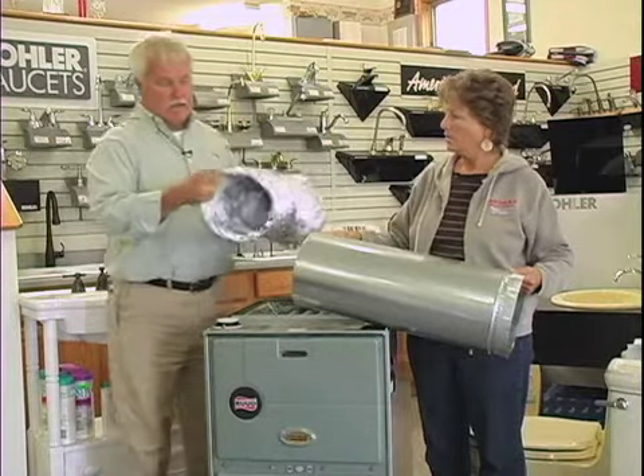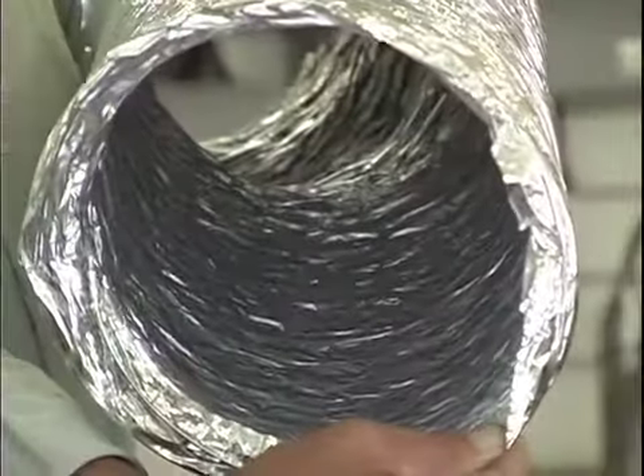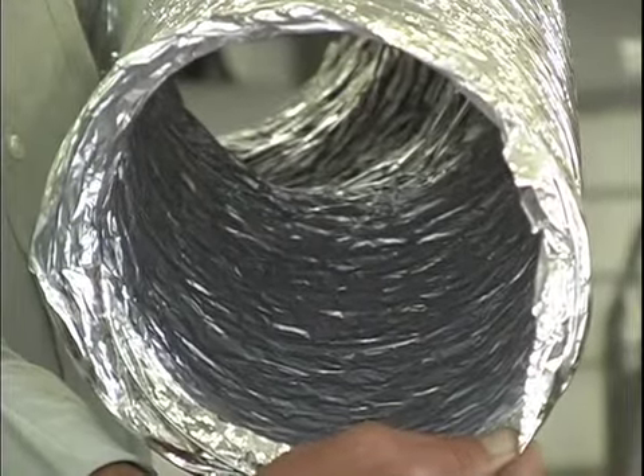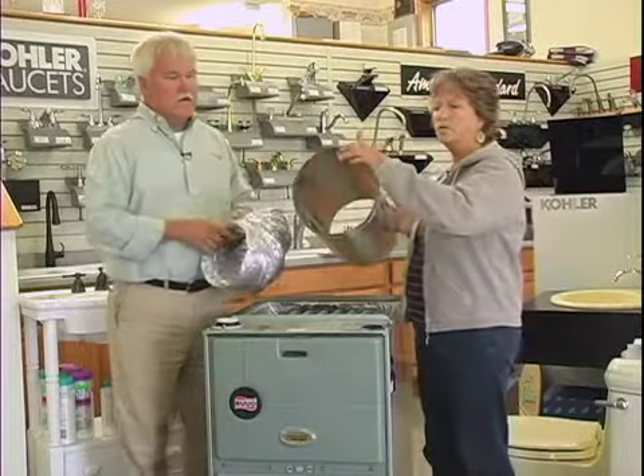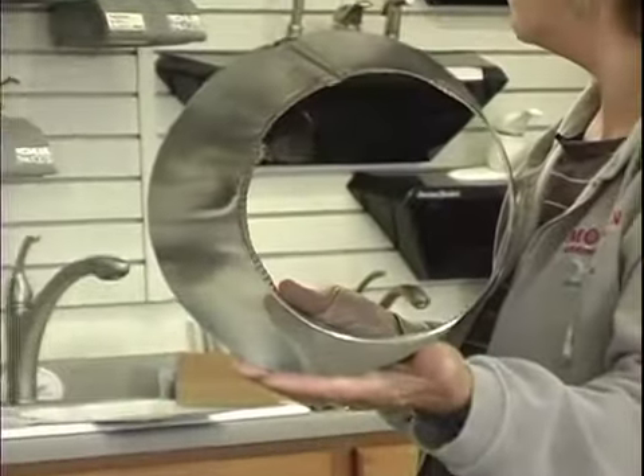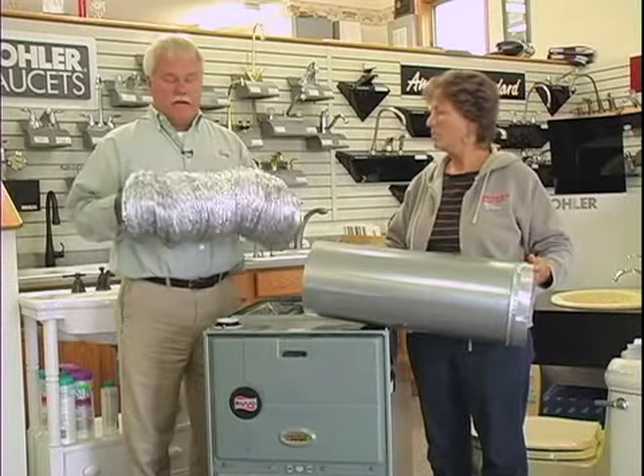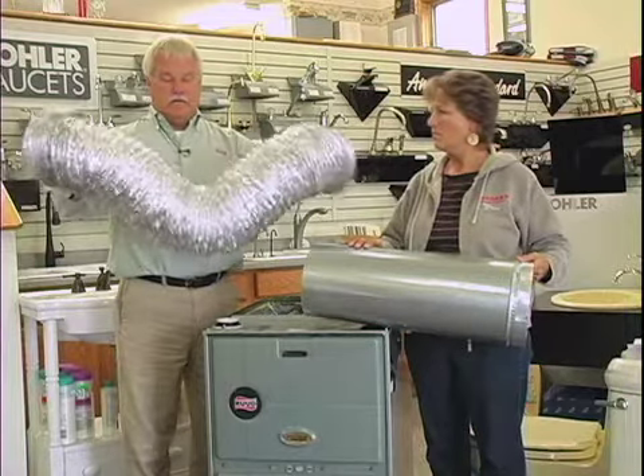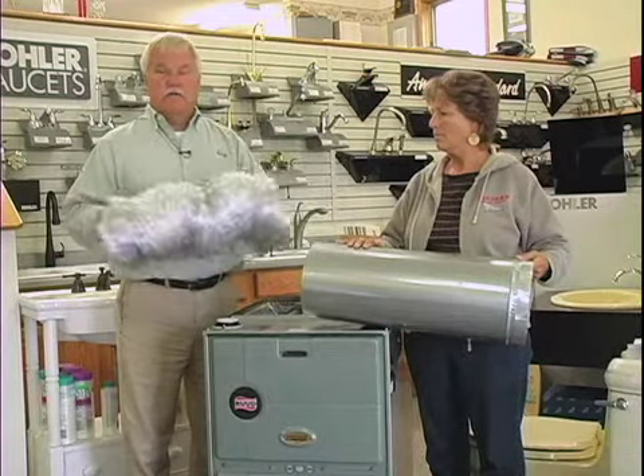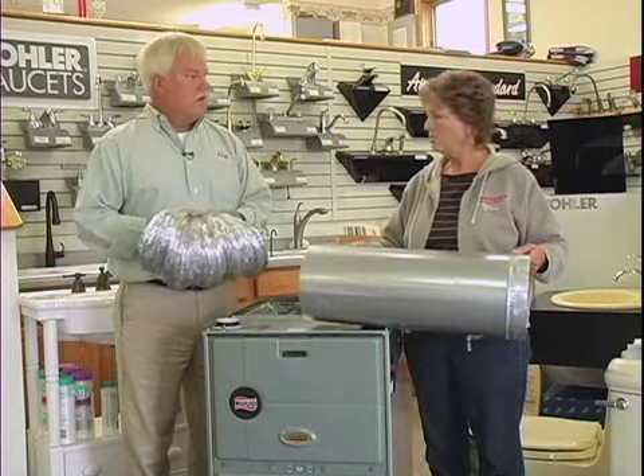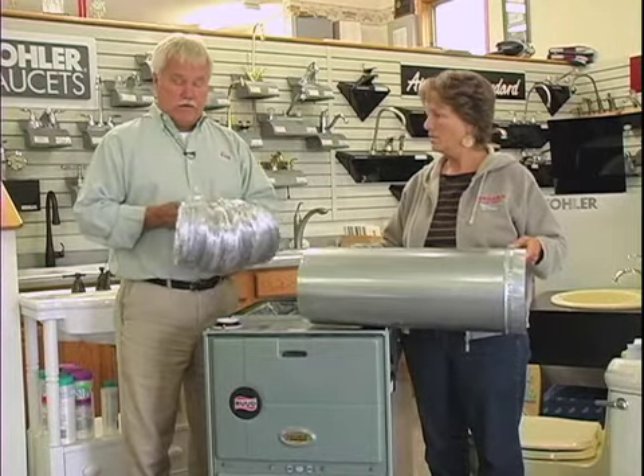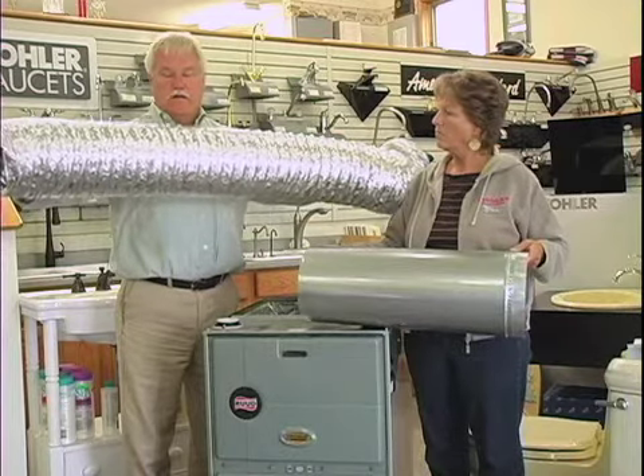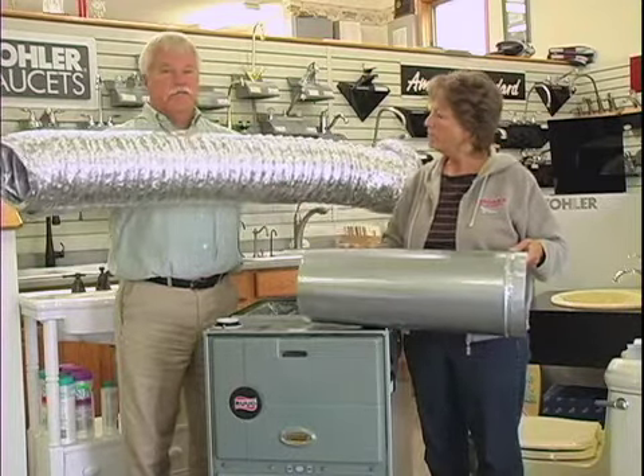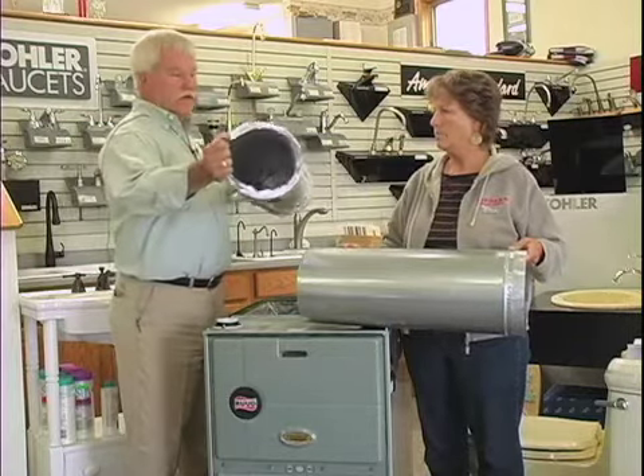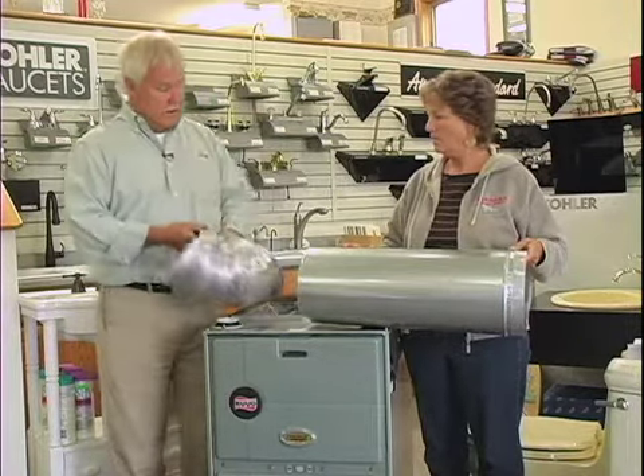If you look at the end of the duct, you can see there are a lot of ridges and a lot of resistance to airflow, as opposed to the piece of pipe that's rigid, very smooth, with very little resistance to airflow. So if you have a duct installed like this, the best thing to do would be to replace it with a hard, smooth pipe for better airflow. At the very least, make sure it's stretched out all the way so it's as taut and smooth as possible. But even smooth flexible duct still has a lot more resistance to airflow than the rigid pipe.